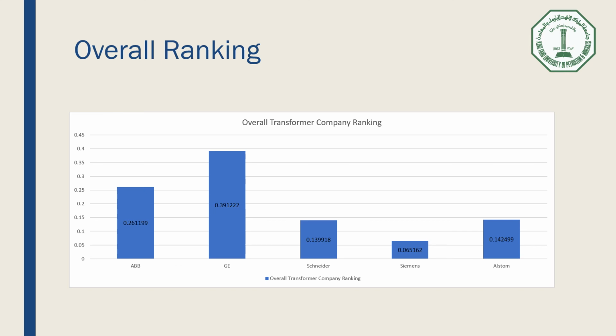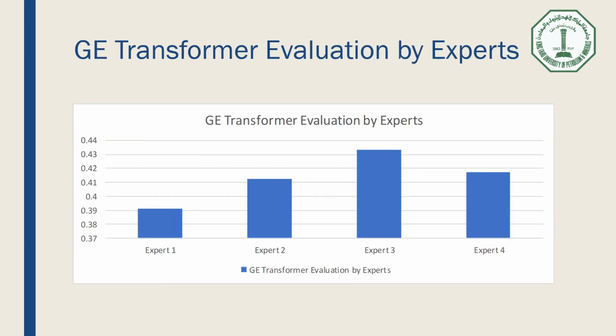If we have a look at the power transmission substations owned by SIC, we will find that almost the same percentages we got apply to the substations regarding the transformer companies. In this slide, we can see the GE transformer evaluation by expert. Expert 3 gave the maximum evaluation for GE, 43 point something percent, and the minimum evaluation was by expert 1, 39 or something, as we can see in the previous slide.